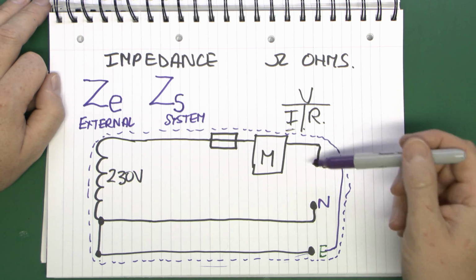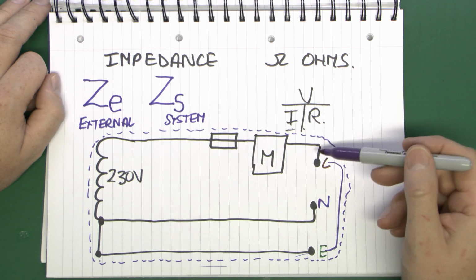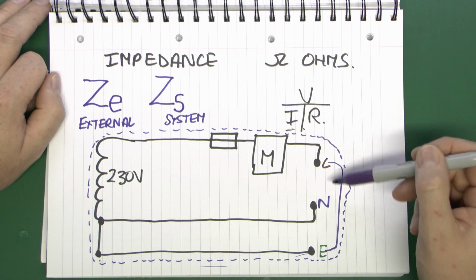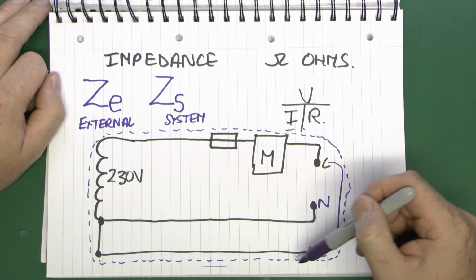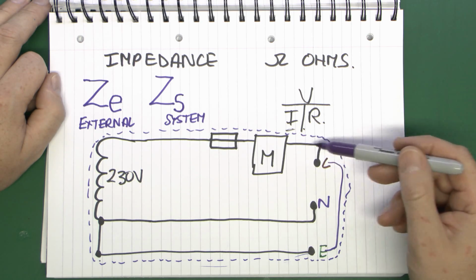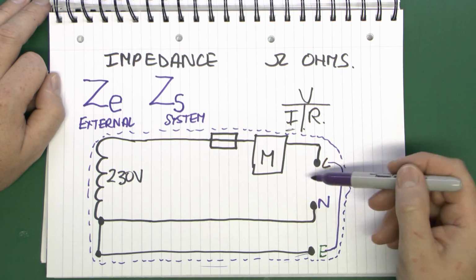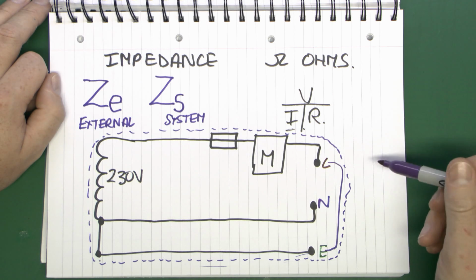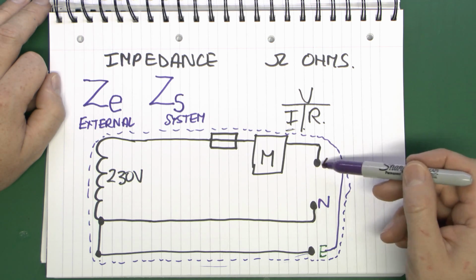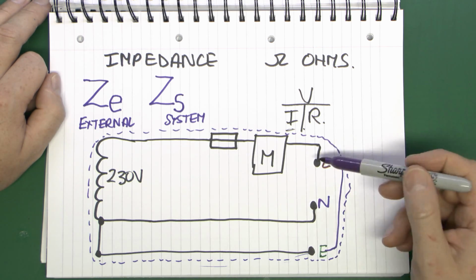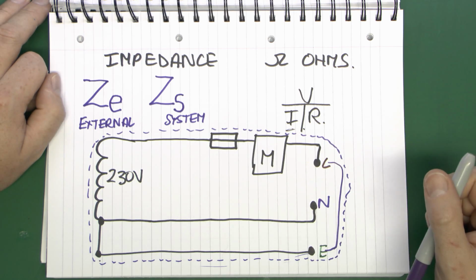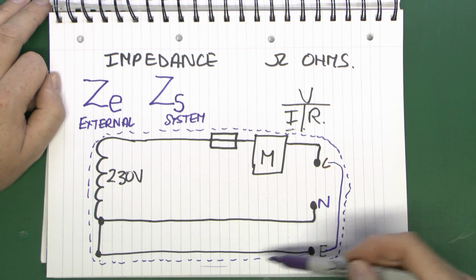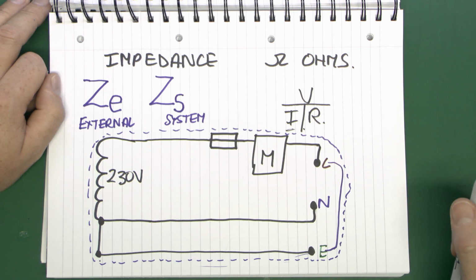But suffice to say, there's a couple of possible options, one of which is to apply a certain amount of load on the end here so a known current will flow. And because you're applying a current flowing through basically a resistance, the voltage here will drop. And by combining the voltage drop at this point and the resistance and the current that's flowing, you can then calculate the estimate of what the total impedance of the system is.